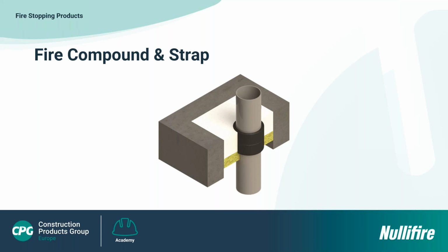So some people ask why compound and not concrete. The main reason is that concrete shrinks when it cures and compound expands to ensure a proper seal. So concrete, if it shrinks, could cause cracks, which could cause smoke to come through. So with the compound, you don't get that.